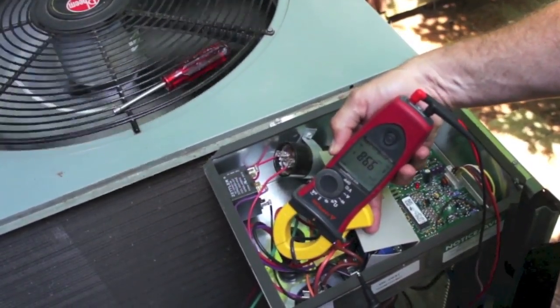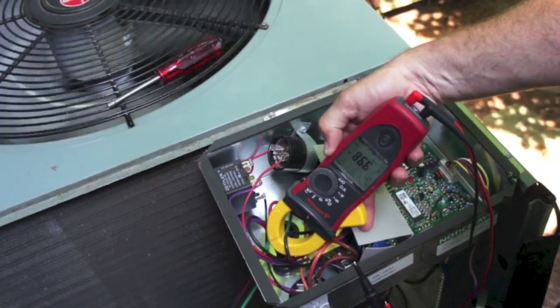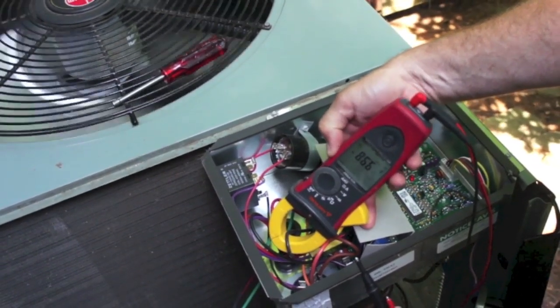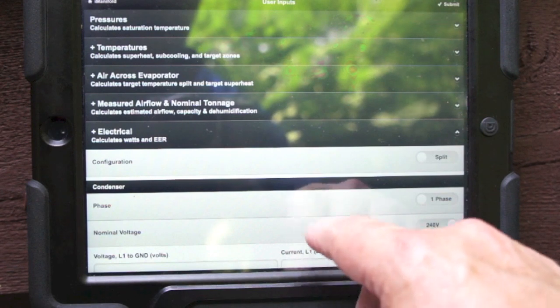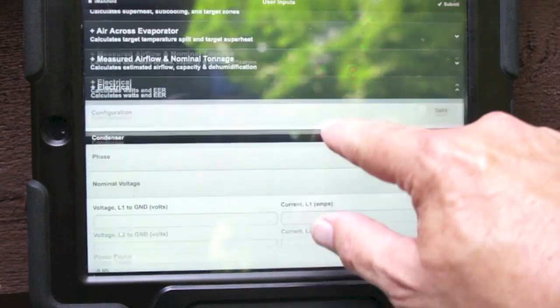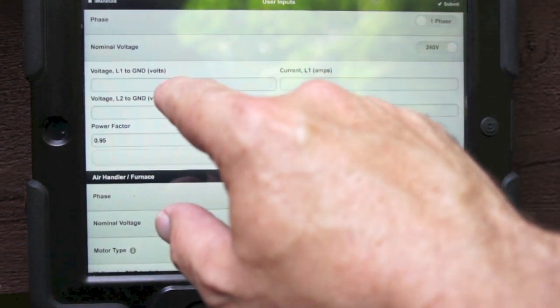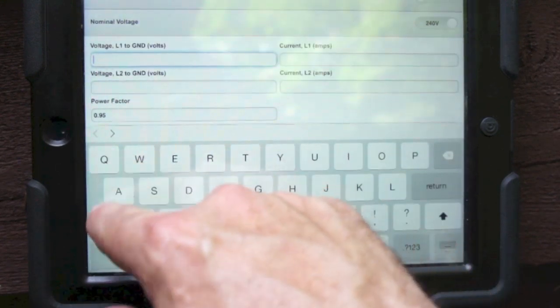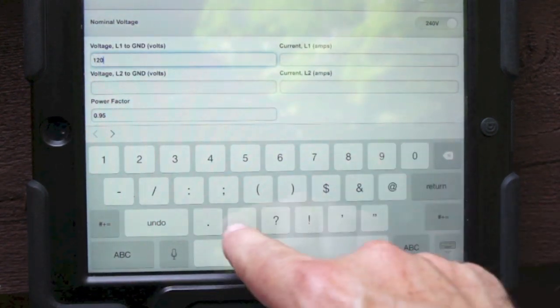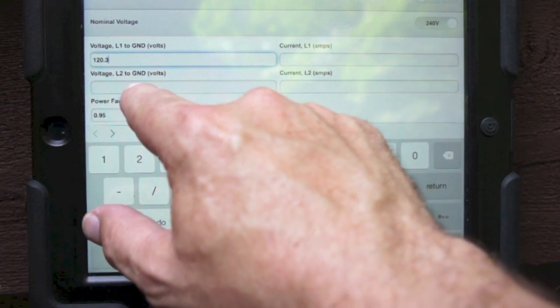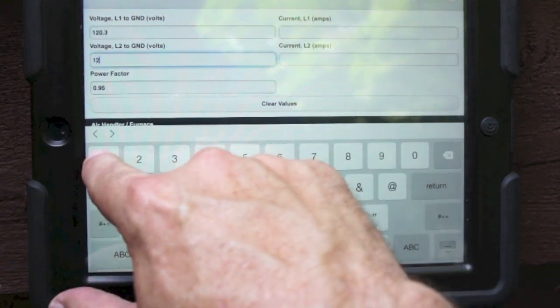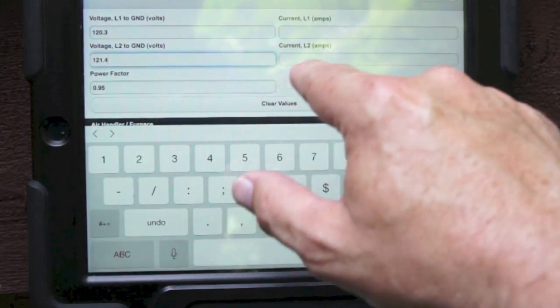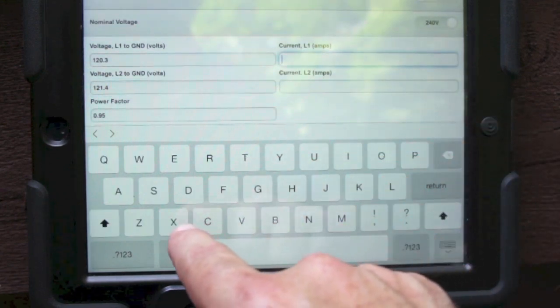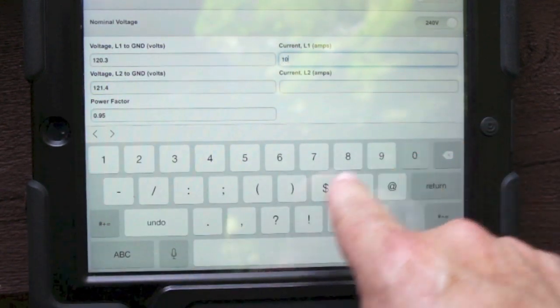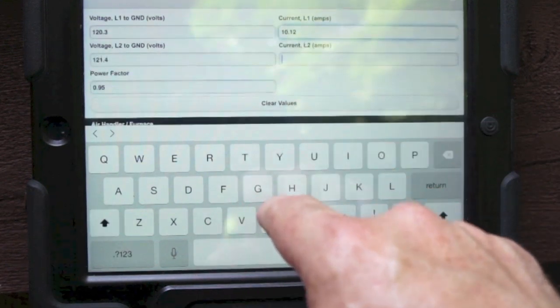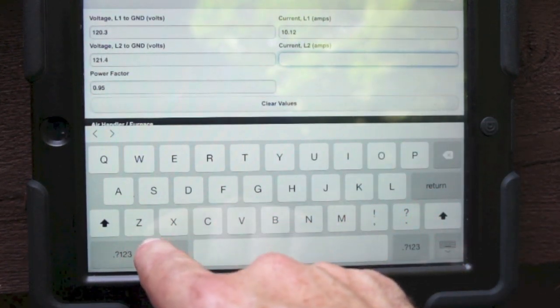and 9.97. So we'll go ahead and put those into the app, and we'll have EER. Okay, so let's go ahead and put our electrical measurements. This is already configured as a split system, single phase, 240 volt. So those measurements were 120.3, 121.4, current on L1 was 10.12, current on L2 was 9.97.